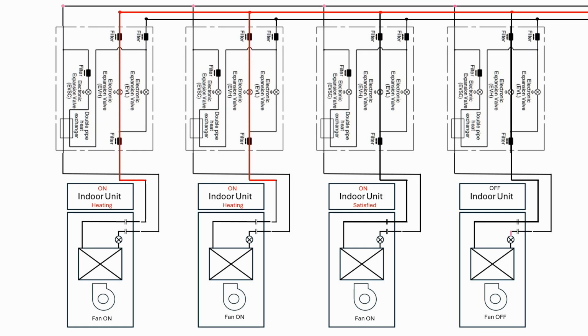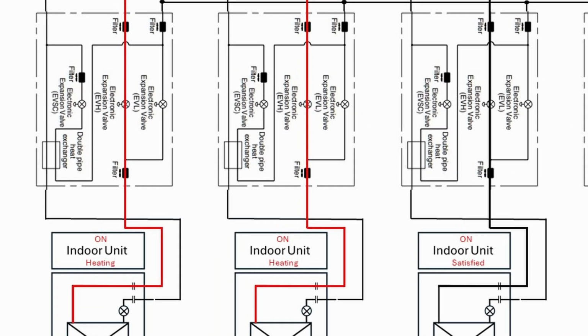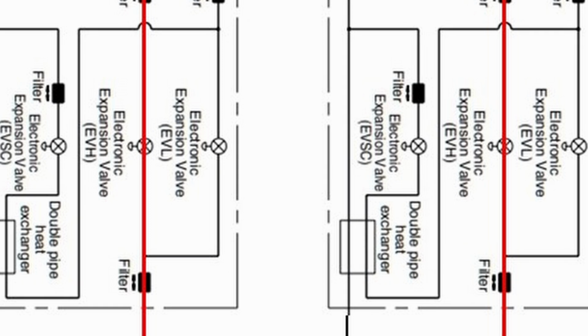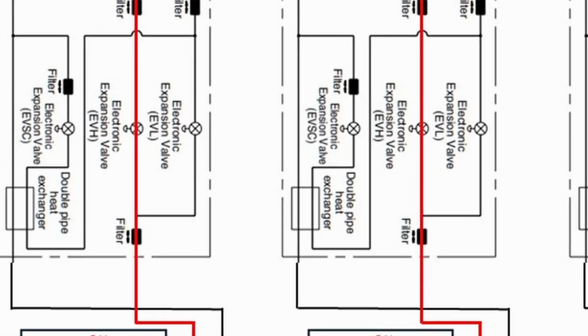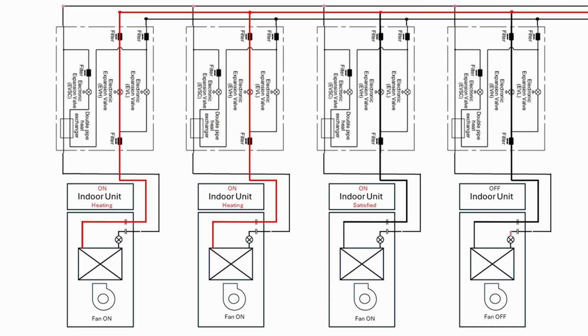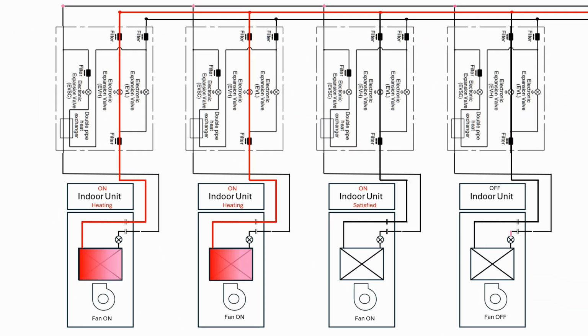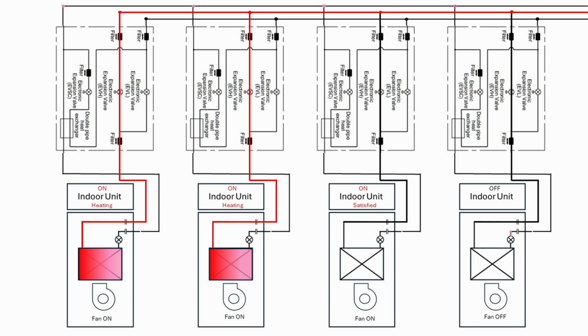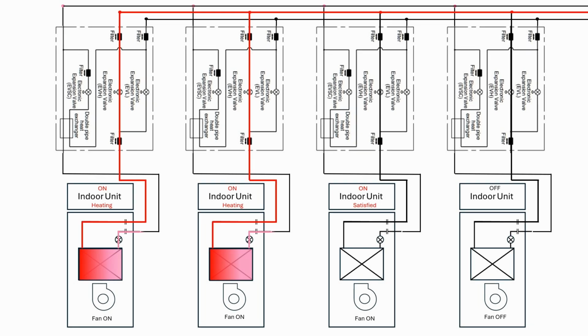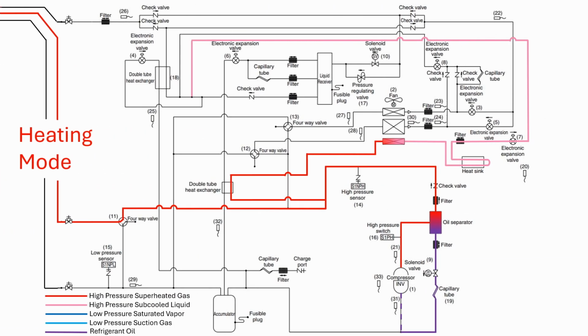As the superheated vapor refrigerant enters the branch selector on the high pressure line, it passes through an electronic expansion valve which is pulsed wide open and not metering. It allows the refrigerant to flow freely to the indoor heat exchanger. As the superheated vapor travels through the heat exchanger, it is subcooled into a liquid, and the heat removed from the refrigerant is given off to the space. The liquid refrigerant leaving the indoor heat exchanger then travels back through the branch selector on the liquid line and is returned to the outdoor unit.